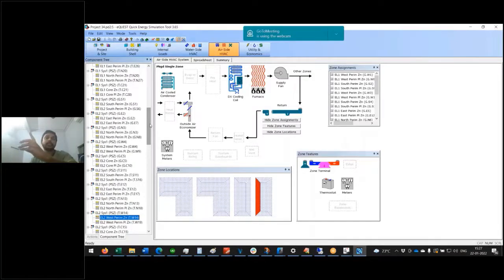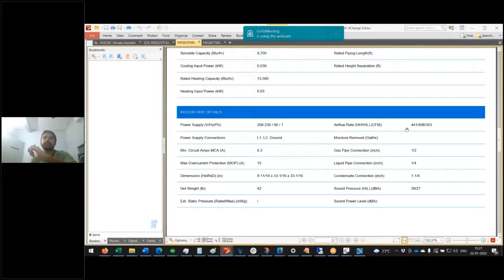But in the proposed case, you really cannot model anything other than what is given in the data sheet; that has to be followed. So for example, 441, you cannot increase this flow. In the base case, because it is auto-sized, yes, you can increase the flow, but definitely not in the proposed case.